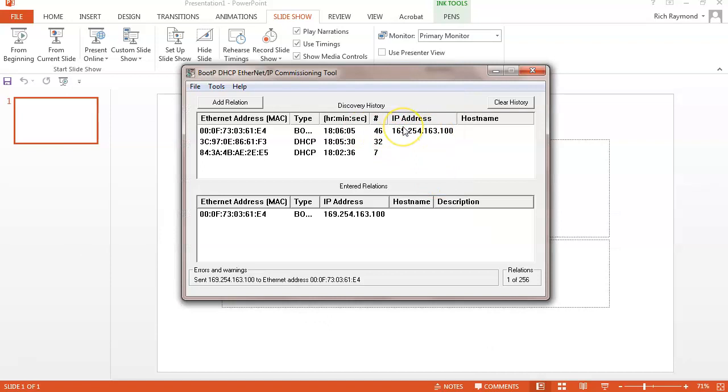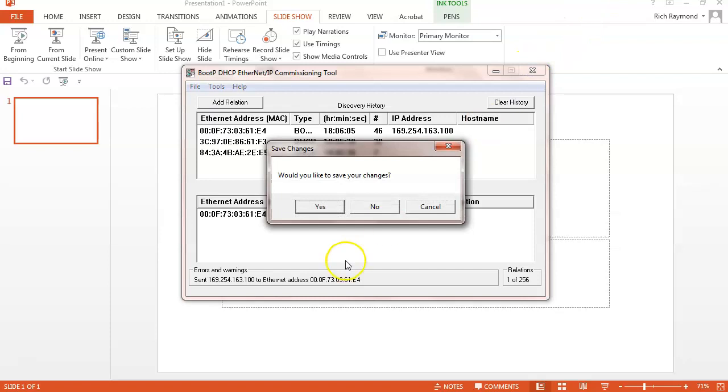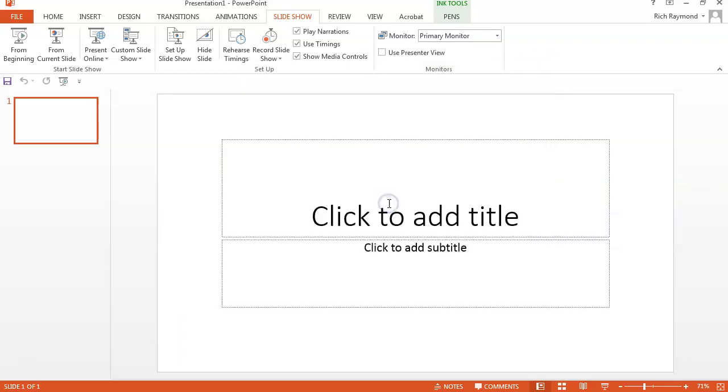Okay, so it got it, right? I'm going to double check it's there, so we should be able to. So anytime your PLC says that, what does that mean? It says, I'm unable to communicate with your PLC. What could be wrong? Well, it could have lost its what? Could have lost its IP for some reason, right? Or your cable that you got connected up might be wrong. Unfortunately, with the new CompactLogix, you can't go in and see the IP that's actually there. It shows you the MAC address.